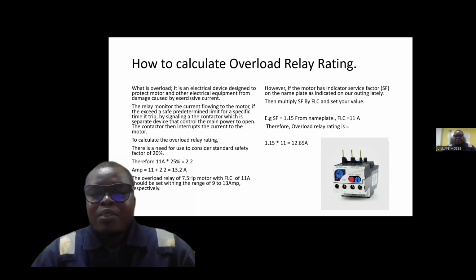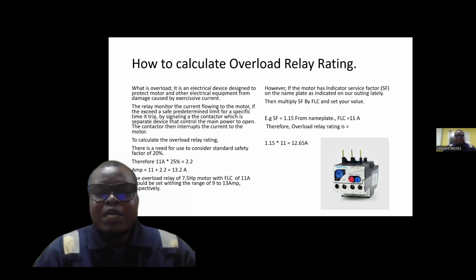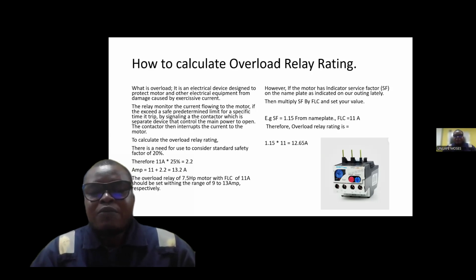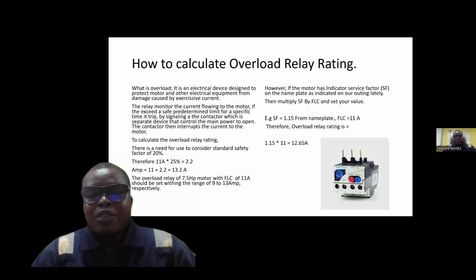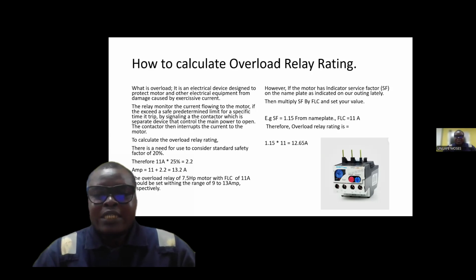And there are other ways to do this. What are the other ways? The other way is for you to consider the indicated service factor. The service factor is always located on the nameplate of the motor that has been supplied. And when you check the service factor in this scenario, it is 1.15. Then you use the 1.15 to multiply our FLC, the full load current, which happens to be 11 amps. When you multiply it, you have 12.65 amps. This 12.65 amps now becomes the amperage of our overload relay rating. Now, in setting this relay, you set it within the range of 9 to 13 amps. Remember, some installers always set the rating at the FLC.